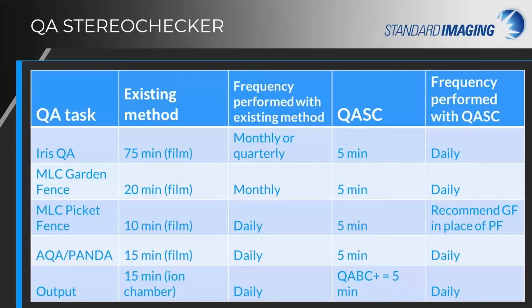It is a recommended daily test. However, it's only a subjective test without any recommended test criteria to measure against. Whereas the garden fence test, recommended for monthly QA, does have test criteria and error thresholds recommended by Accuray. Each of these tests takes the same amount of time to run on the machine, so why not perform the garden fence test daily with the QA StereoChecker? Knowing the MLCs pass those 4 test criteria is surely a great way to start the day's treatments with the highest level of confidence.